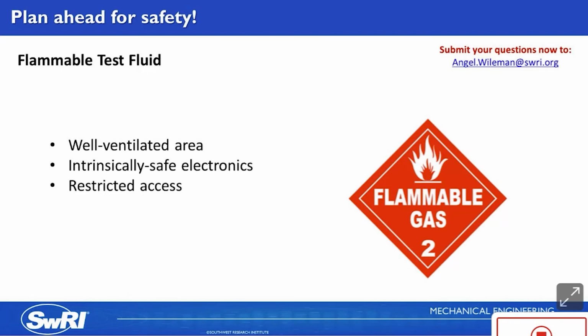The test area should be clearly marked with warning signs that indicate the presence of flammable gases. Because the 15-foot rule is hard to visualize, I would recommend putting up a fence or some kind of a barrier around the test stand to keep non-rated electronics out of the space. And the warning signs placed along the barrier should indicate no smoking or hot work nearby. Lastly, portable methane detectors should be worn by personnel entering the space to detect when methane vapors are present.